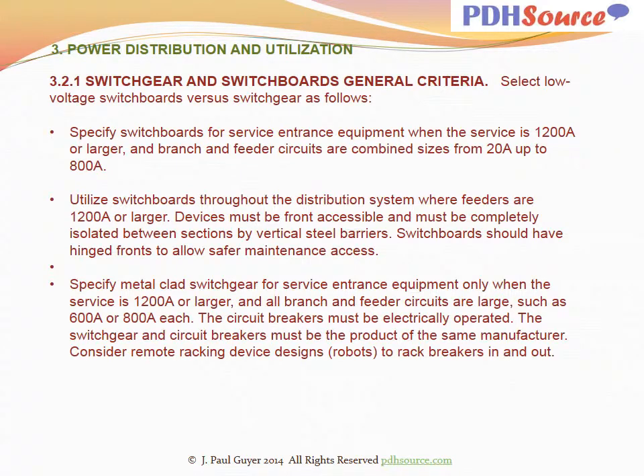With regard to switchgear and switchboards criteria, select low voltage switchboards versus switchgear as follows. Specify switchboards for service entrance equipment when the service is 1200 amps or larger and branch and feeder circuits are combined sizes from 20 amps up to 800 amps. Utilize switchboards throughout the distribution system where feeders are 1200 amps or larger. Devices must be front accessible and must be completely isolated between sections by vertical steel barriers. Switchboards shall have hinged fronts to allow safer maintenance access.